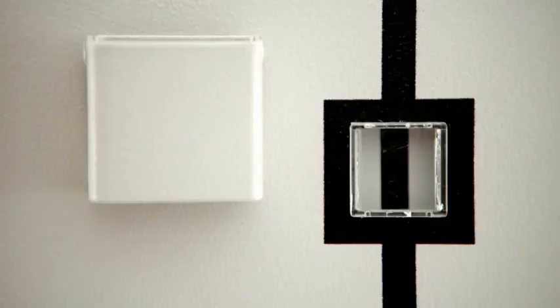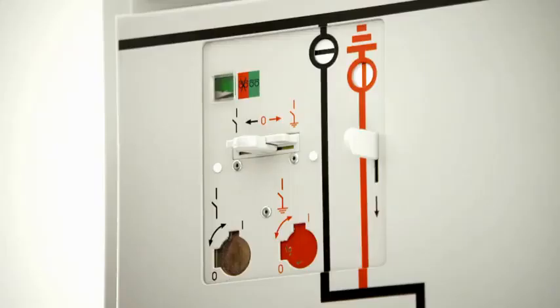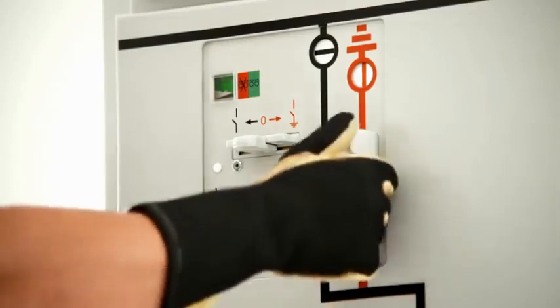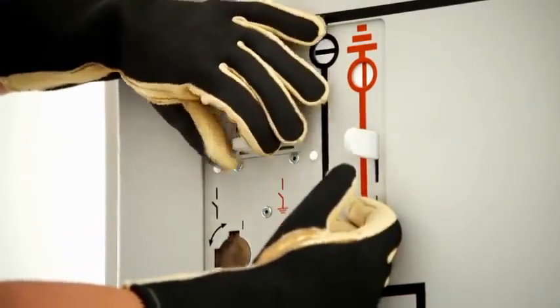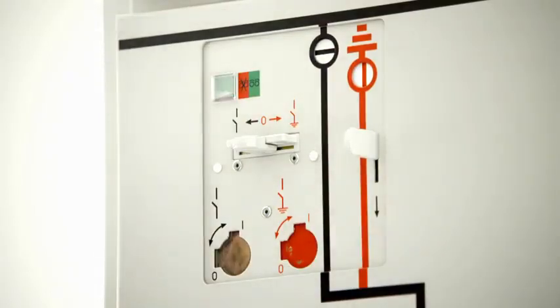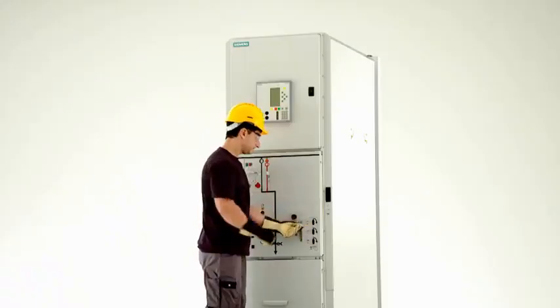The mechanical interlocking between the circuit breaker and the three position disconnector also makes it impossible to operate the three position disconnector. This prevents mal-operation and is a definite plus for personal safety.